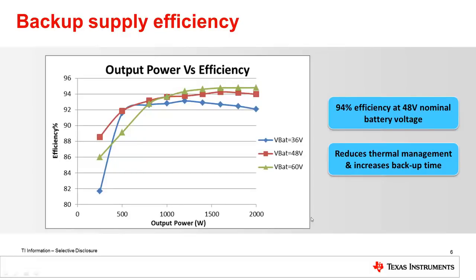We now look at the efficiency results of the system when operating in the backup mode. The system achieves a full load efficiency of greater than 94% at 48 volt nominal battery input voltage, and the efficiency goes to above 95% at 60 volt battery input voltage. Overall, the high efficiency helps in reducing the thermal management while increasing the battery backup time provided by the system.